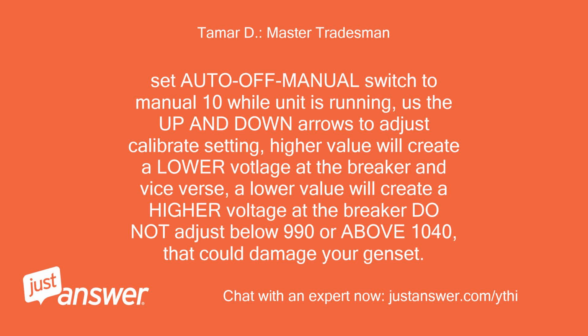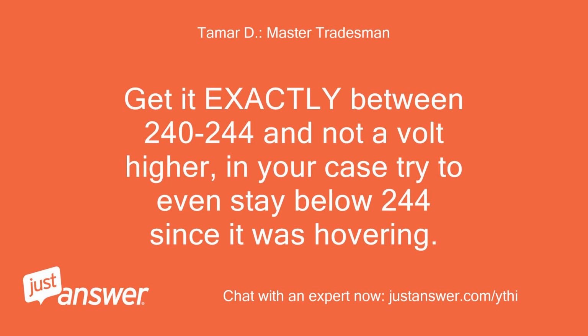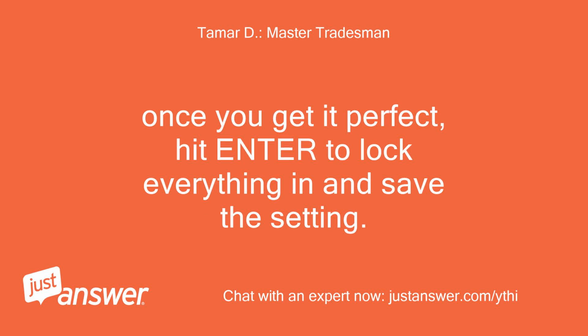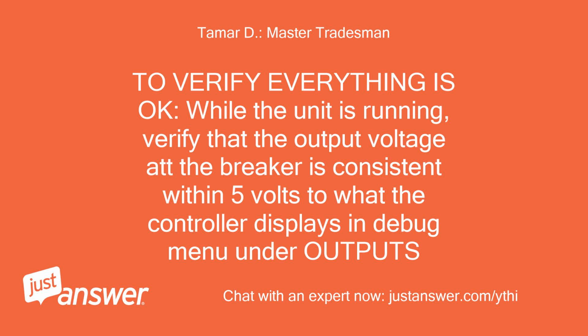9. Set the auto off manual switch to manual while the unit is running. 10. Use the up and down arrows to adjust the calibrate setting. A higher value will create a lower voltage at the breaker and vice versa. A lower value will create a higher voltage at the breaker. Do not adjust below 990 or above 1040, that could damage your genset. Get it exactly between 240 to 244 and not a volt higher. In your case, try to even stay below 244 since it was hovering. Once you get it perfect, hit enter to lock everything in and save the setting. To verify everything is okay, while the unit is running, verify that the output voltage at the breaker is consistent within 5 volts of what the controller displays in the debug menu under outputs.